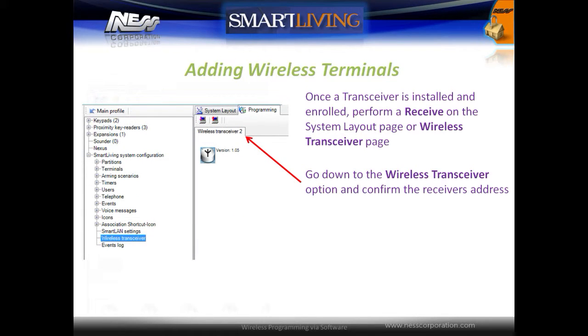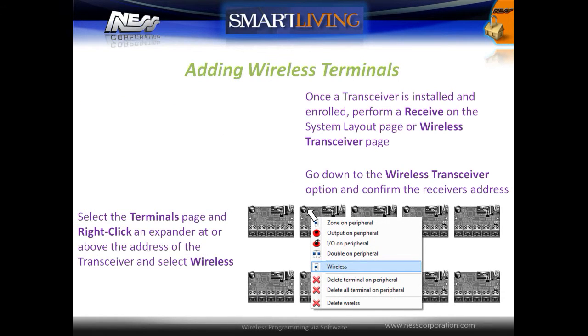Select the wireless transceiver page and confirm its address. Then select the terminals page and right click on an expander that is at or above the address of the transceiver. Select the wireless option to set the expander as a wireless expander. A wireless symbol will indicate the expander as wireless. The expander is reserved as a wireless expander but is currently greyed out because terminals have not yet been added from the system layout. Open the system layout page and double click the expander module used for wireless — the wireless expander is now blue and ready to be configured. Be sure to send the terminals page before enrolling devices.